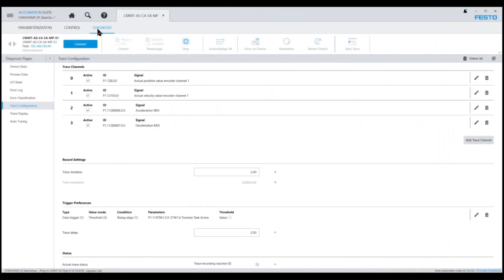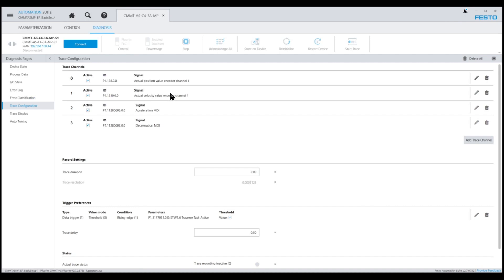Let's review the trace configuration settings in the Festo Automation Suite. The trace settings can be found under the diagnostics tab and the trace configuration page. As you can see here, I have created four trace channels including actual position, actual velocity, acceleration MDI, and deceleration MDI.